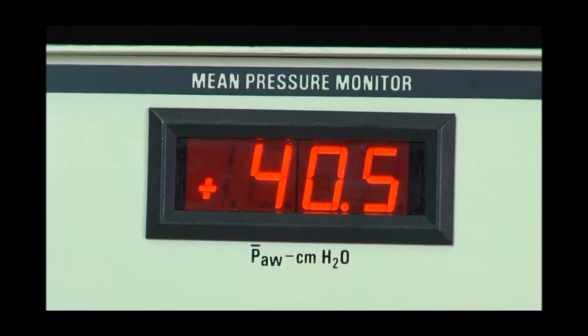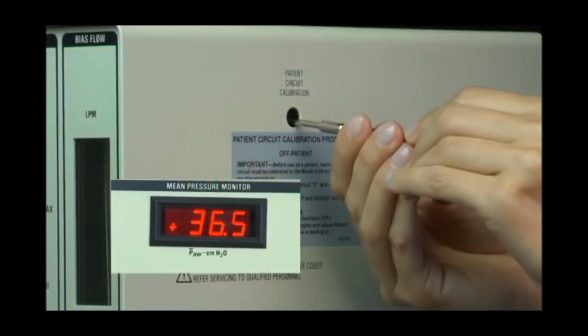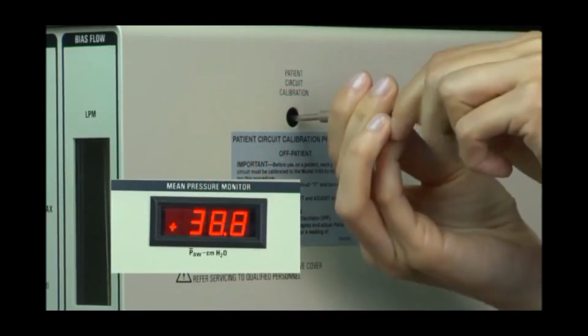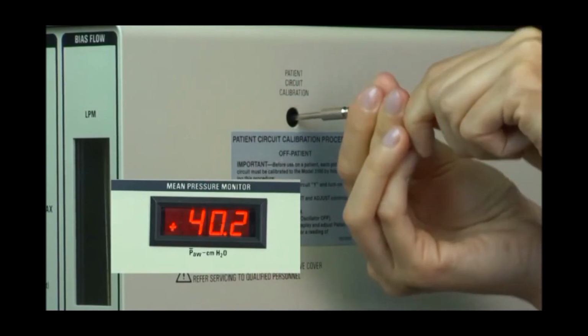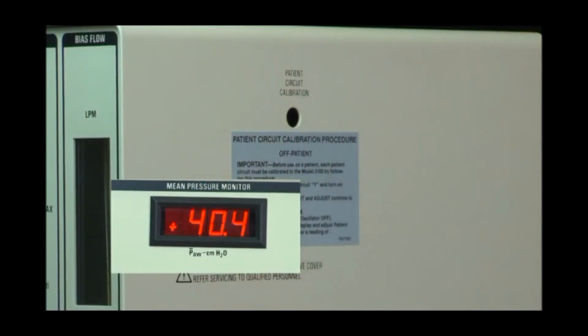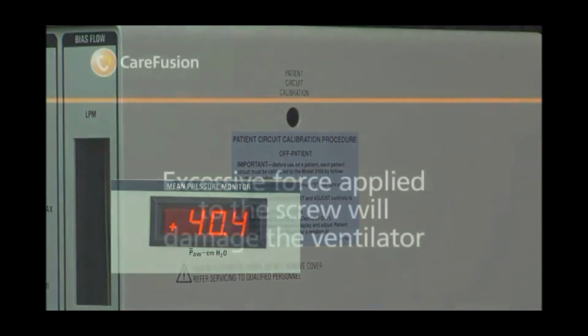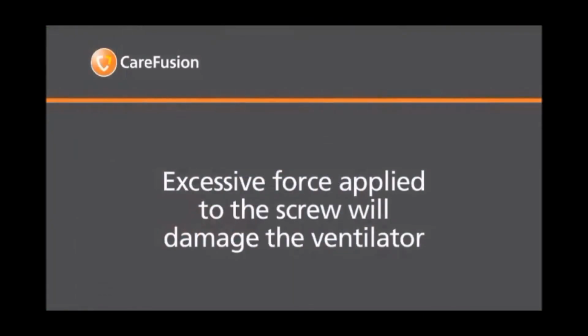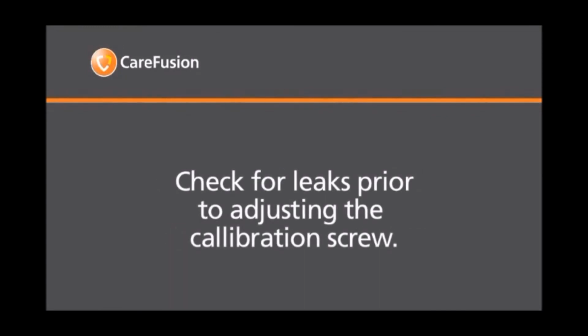If necessary, adjust the patient circuit calibration screw, shown here, to achieve a mean airway pressure of 39 to 43 centimeters of water pressure. Caution should be used when performing this procedure, since excessive force applied to the screw will damage the ventilator. If this pressure range cannot be achieved, remove any humidifier and check the circuit for leaks or damage.